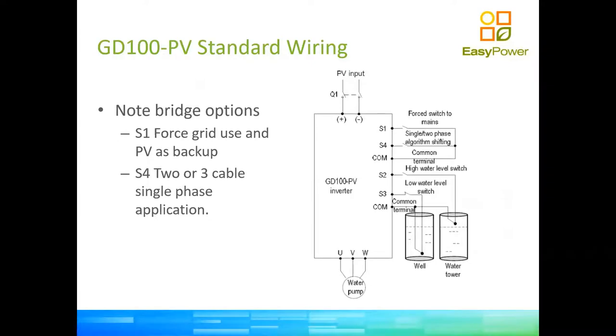The GD100 comes with digital inputs — four auxiliary contacts: S2, S3, and S4. These can be used to control the inverter against water sensors. You can have a dry-run sensor, which comes with virtually all borehole pumps so the pump doesn't run dry, and a sensor that stops the pump inverter when the tank is full to prevent overflow. When the tank drains overnight, the float will drop and the inverter will start automatically in the morning as soon as there is solar power available.